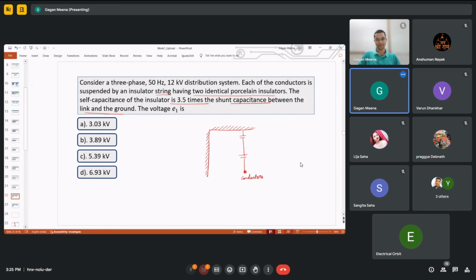So for n units in the insulator string, there will be n minus 1 capacitances, Cs, between the string and the ground. This is the link capacitance. There is only one link connecting the two units of insulators, so the capacitance between this link and the ground, since the tower is grounded, is Cs.